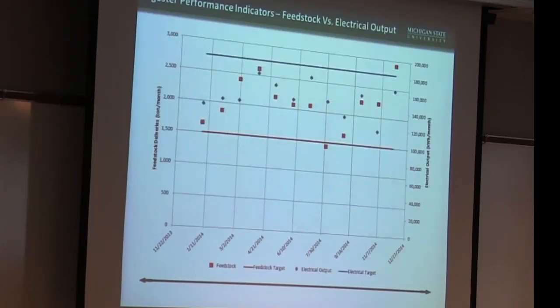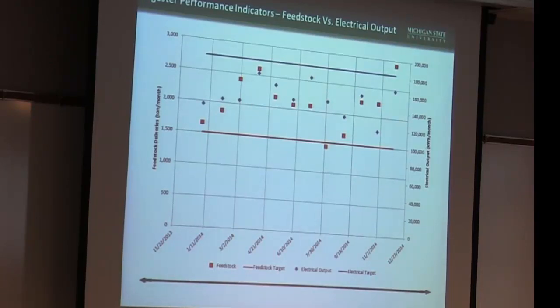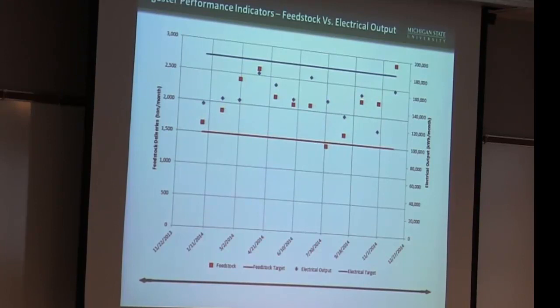Looking at charts put together last night: the red line is our target for feedstock on a monthly basis. Because we had so much manure, we were almost always well above our feedstock target. For electrical production, our target was about 183,000 kilowatt hours per month. We were generally below that, and at different times of the year farther below than others. Overall for the year, we averaged about 80% of our target. We had mixer issues, clogging issues, and a feedstock blend that was much less energy-dense than anticipated. The fact that we operated at 80% was actually above what I had projected — I thought we'd be at about 70%, so we did a little bit better. I believe by early spring we will be at 100% of our target.